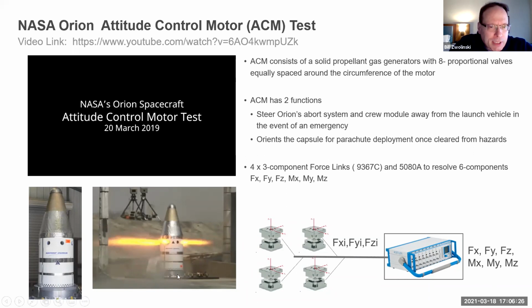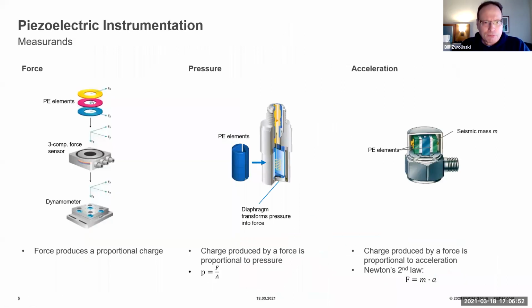Mounting the dynamometer in the base is very common, and the thruster action is above, isolated from any heat or any issues caused by that. But this is a very typical piezoelectric application. Now, it's also a very typical strain gauge application too. So I'm going to touch upon that in a minute, because some folks are more familiar with strain gauge technology. But in terms of piezoelectric instrumentation, we're going to primarily focus on force, with some acceleration and some pressure in this presentation.